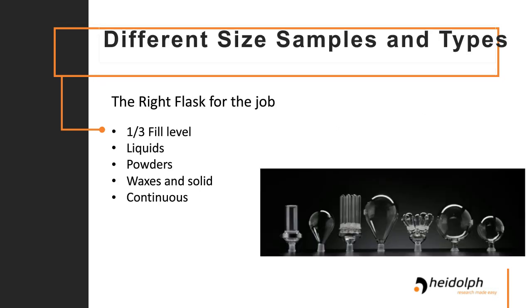When you're dealing with different size samples and types, it's all about finding the right flask for the job. Size-wise, you always want to shoot for about a 1/3 fill level. So if you have 2 liters of solvent or 2 liters of material, you want to be looking for a 5-liter flask, or if you're okay with doing 300 mils at a time, a 1-liter flask might be good for you. You always want to have it sized about right so that you're evaporating at the most efficient level.